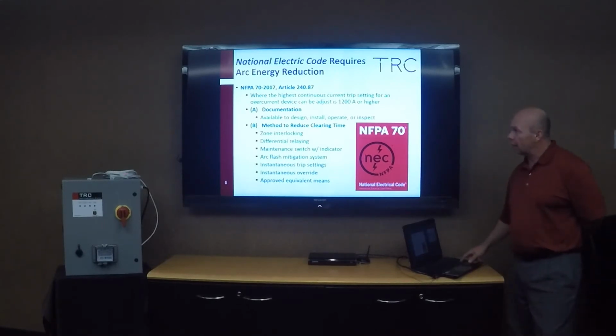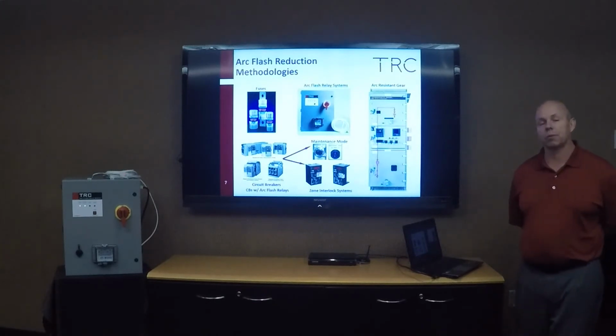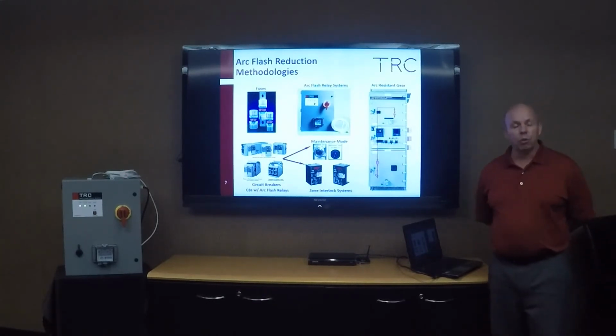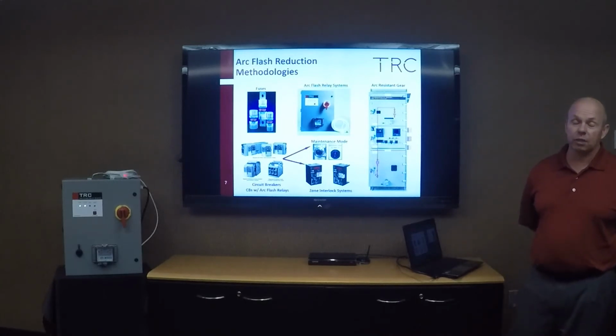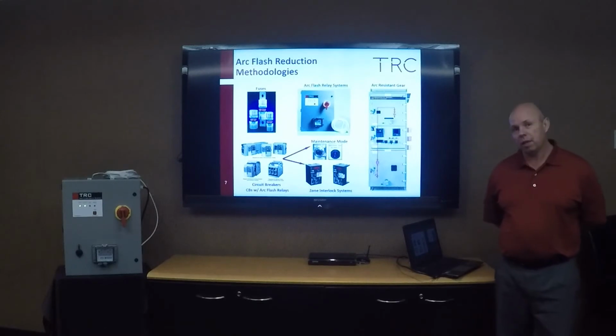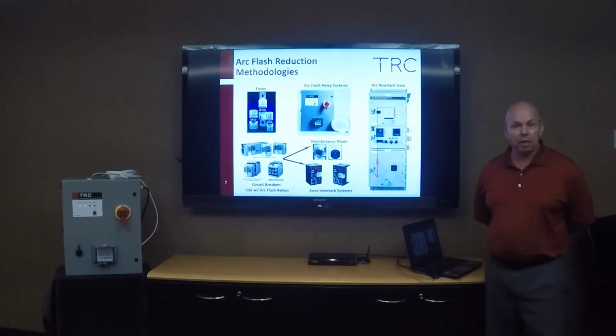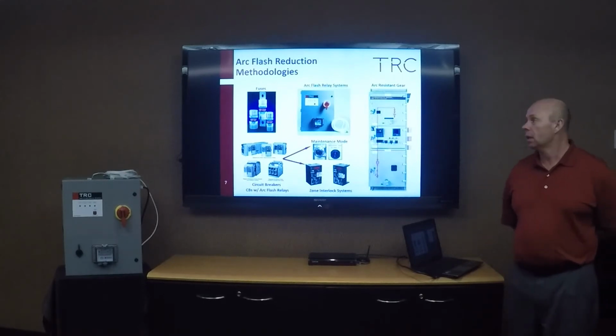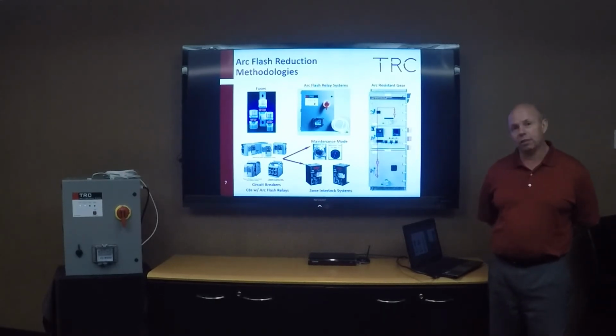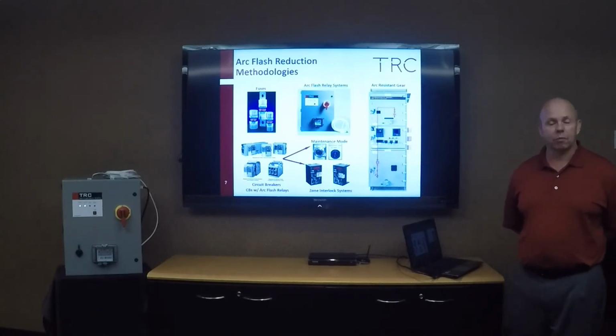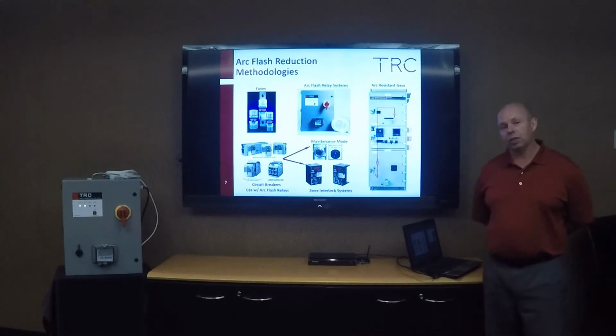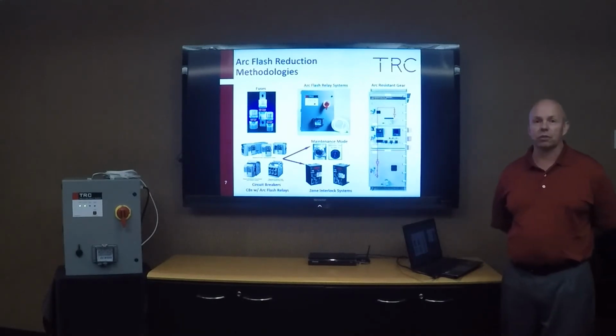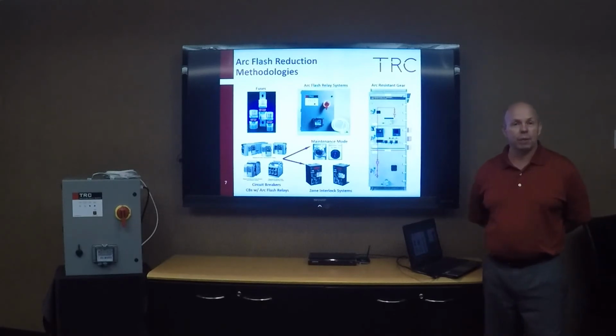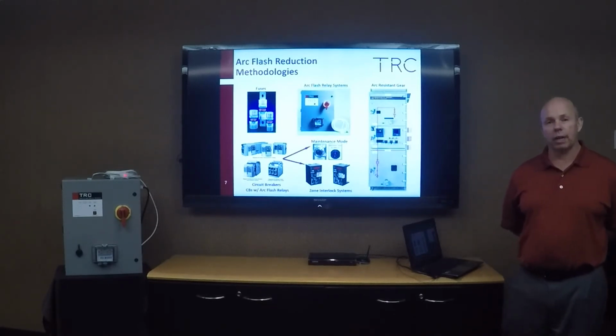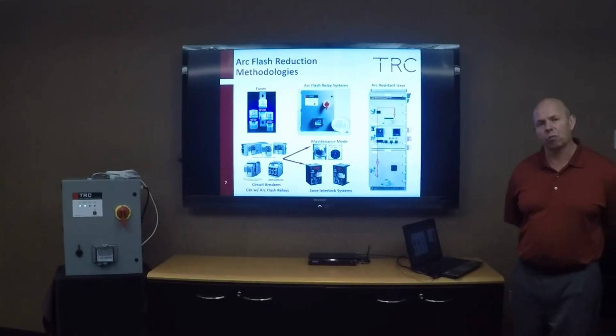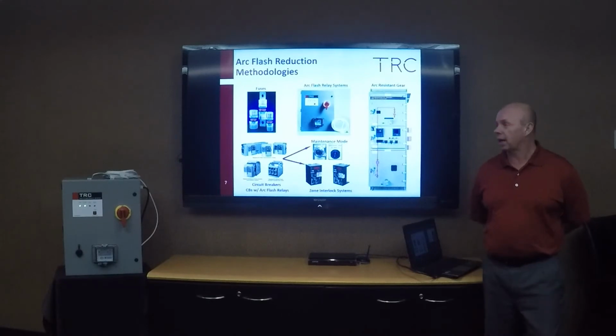And so let's take a little closer examination of some of these methods of arc flash reduction. So one common approved method for arc flash reduction is actually the use of fuses. Fuses have been used for many, many years to reduce incident energy, mainly because they have a very fast trip time. When you design a brand new power system and you design it with fuses throughout, you can set up some very good coordination. However, you can't just come into an existing electrical system and incorporate fuses upstream to reduce the amount of incident energy, because now you have coordination issues between fuses, circuit breakers, and other relaying that you might have currently inside your equipment.